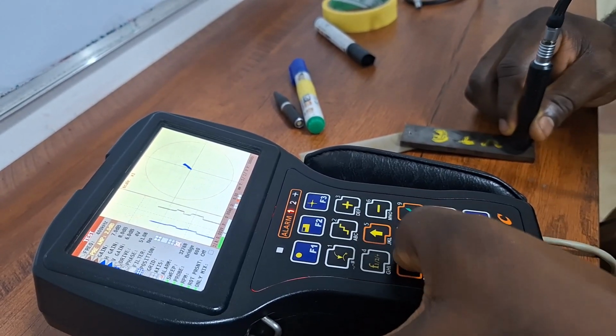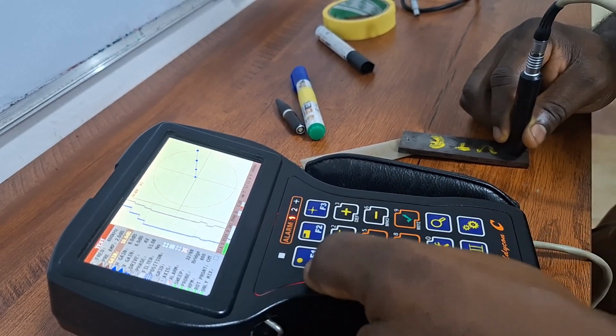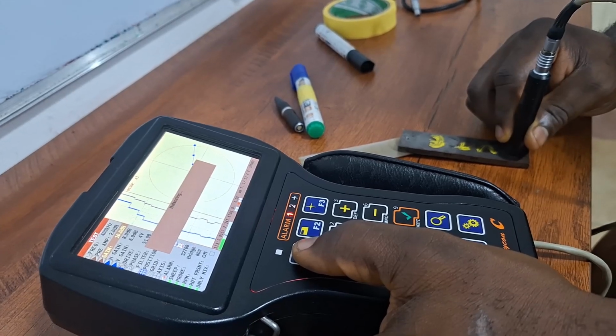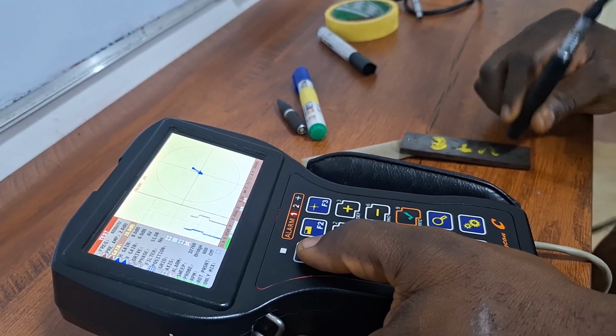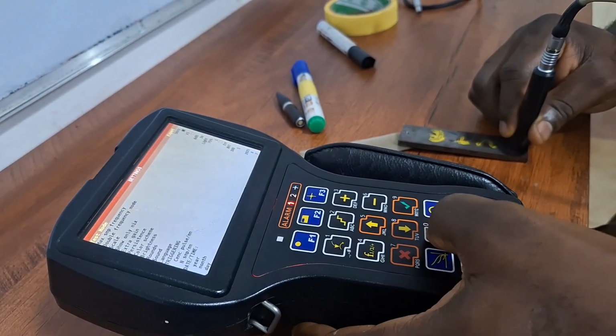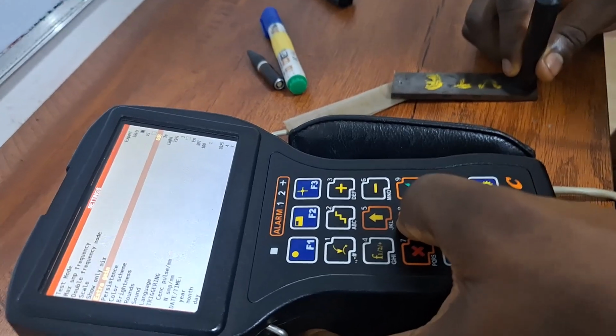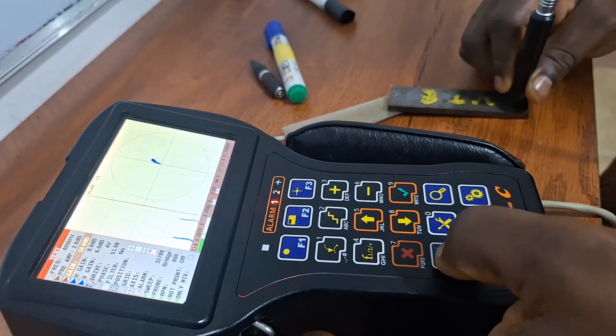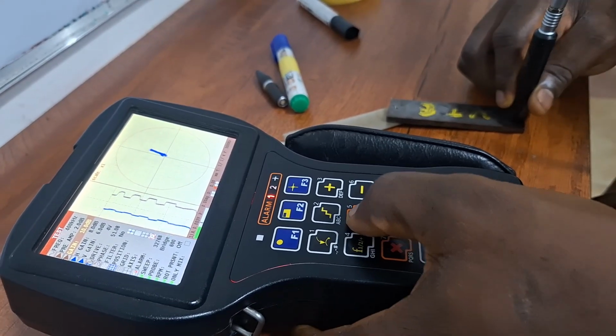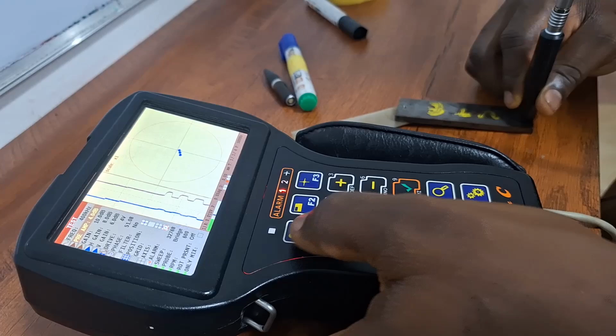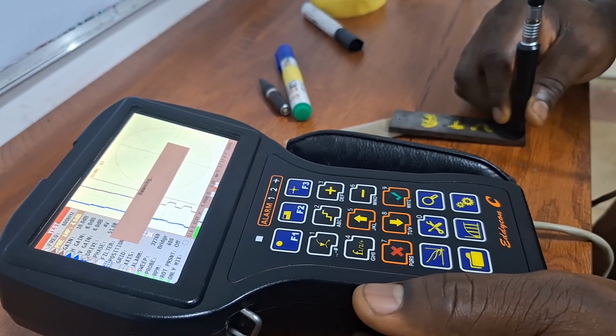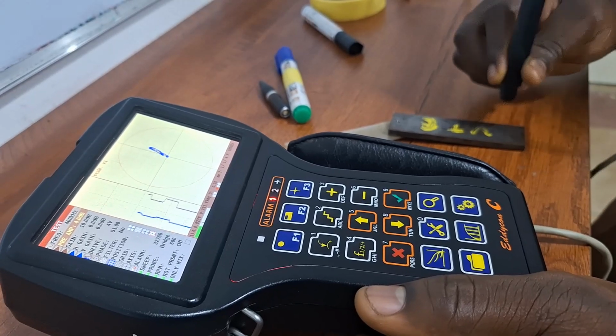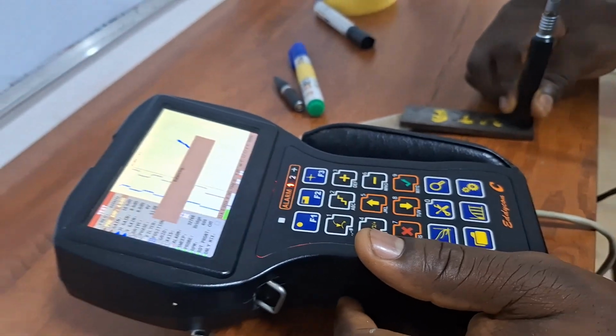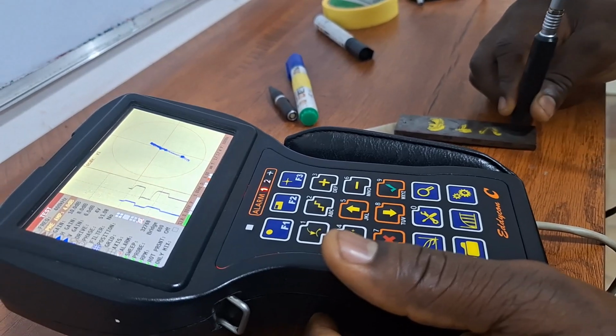If we want the signal to be bigger, we increase the general gain and see what happens. General gain is still low. Let's go to extra gain here, and it's already at 6 dB, so let's not increase it further. So we increase our preamplification again and we balance and see how it comes out. Okay, so we have a much clearer lift-off signal now. So this is our lift-off signal. Balance.